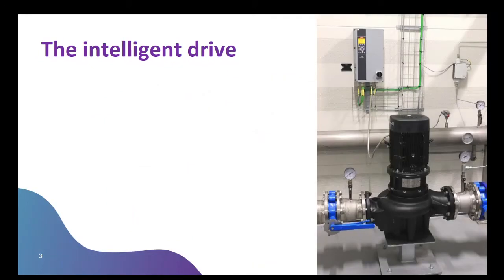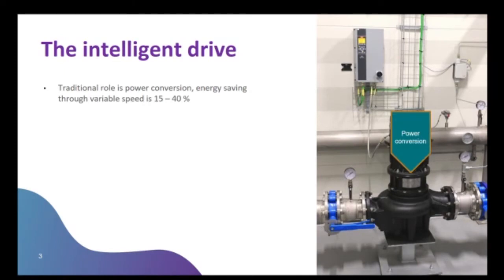And this highlights the importance of using variable speed in water application. But if we look at this example in the picture, you see a variable speed drive that controls a motor, and the motor drives a pump. The pump then pumps water, fresh water in this example. So one role is the power conversion. This is the traditional role where we save 15 to 40% of energy.